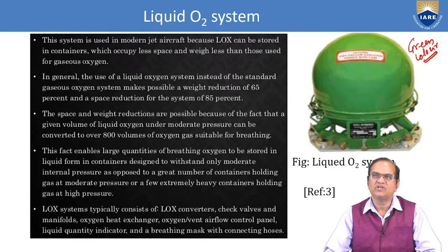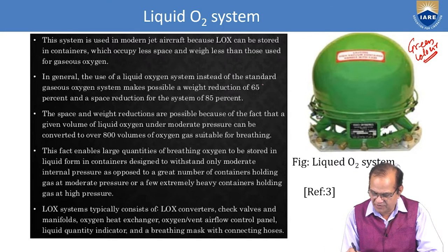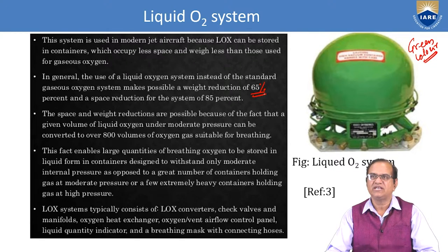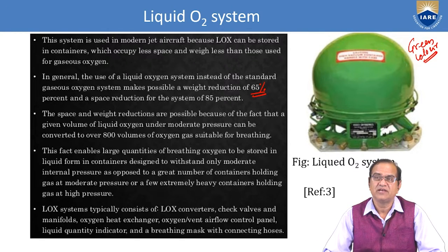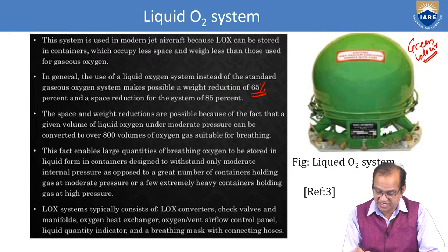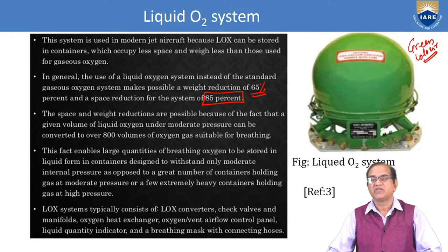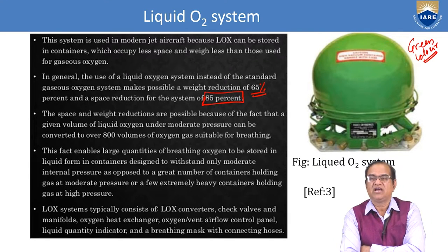In general, the use of a liquid oxygen system instead of the standard gaseous oxygen system makes possible a weight reduction of 65%. A very important point. If you make the liquid, 65% of the weight of your system is reduced, and space reduction of 85% is also achieved. That is the advantage of making liquid oxygen.